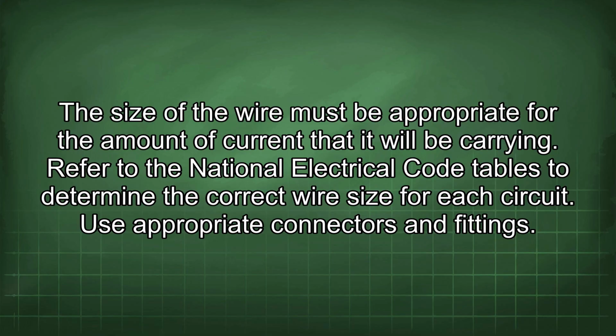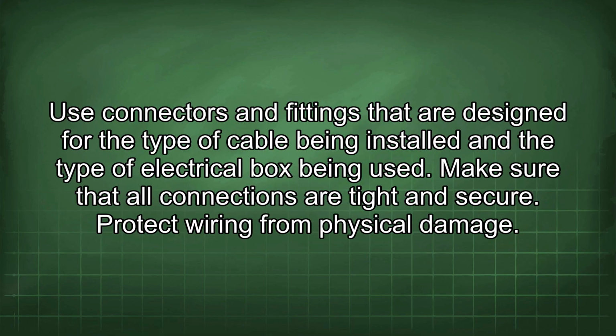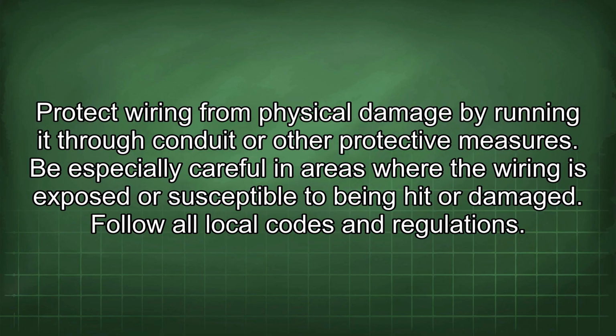Use appropriate connectors and fittings. Use connectors and fittings that are designed for the type of cable being installed and the type of electrical box being used. Make sure that all connections are tight and secure. Protect wiring from physical damage. Protect wiring from physical damage by running it through conduit or other protective measures. Be especially careful in areas where the wiring is exposed or susceptible to being hit or damaged.